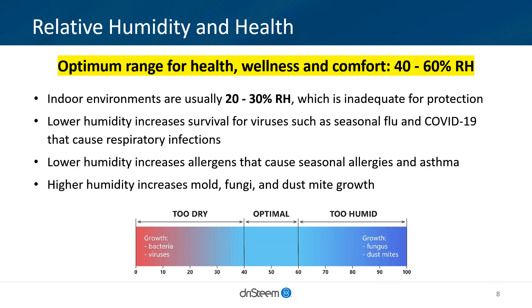The optimal range for human health, wellness, and comfort is 40-60% RH. To many people's surprise, indoor environments are usually 20-30% RH, which is inadequate for protection against common illnesses.